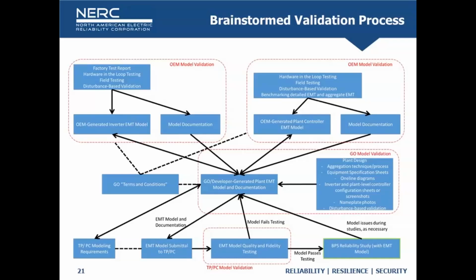Ideally, the GO would also be performing some model quality tests, or the consultant the GO has hired is executing some high-level model quality checks. We really rely on the transmission planner modeling requirements, down in the bottom left there, to specify what those checks are. So if the TPPC doesn't say, hey, I need you to check the model and make sure it passes basic ride-through tests, can handle phase jumps, can provide the right amount of frequency response and dynamic voltage control, and all these kinds of things, then the GO is not going to test it because it hasn't been required.